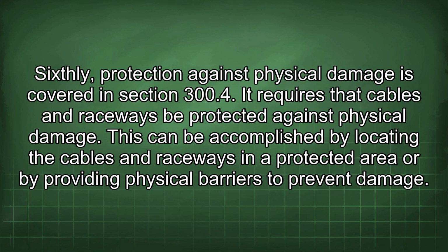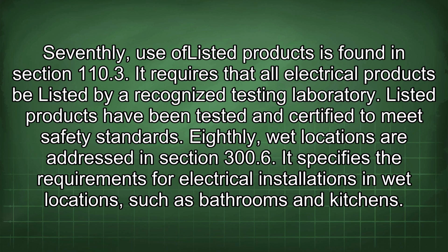Sixthly, protection against physical damage is covered in section 300.4. It requires that cables and raceways be protected against physical damage. This can be accomplished by locating the cables and raceways in a protected area or by providing physical barriers to prevent damage. Seventhly, use of listed products is found in section 110.3.